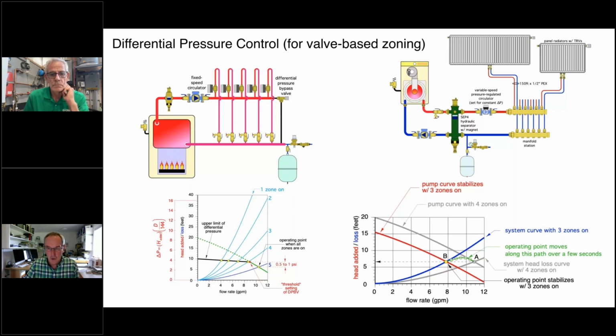We've reduced the flow rate in the system or going through the circulator because one of the zones is closed, but we haven't changed the differential pressure, which means the flow velocity in the zone circuits that remain on stays the same. So that eliminates that noise issue. In extreme cases, it would eliminate erosion, corrosion in a copper elbow, that type of thing. So that has become a modern, in a sense, replacement for a differential pressure control.